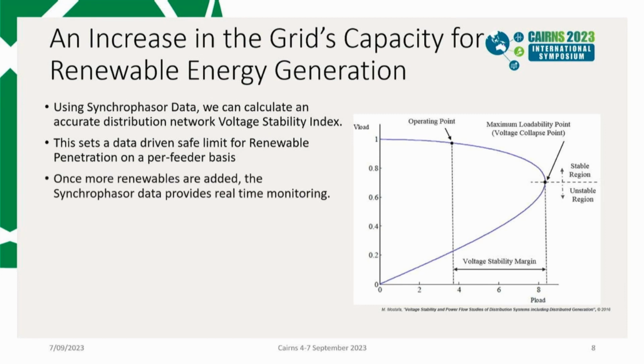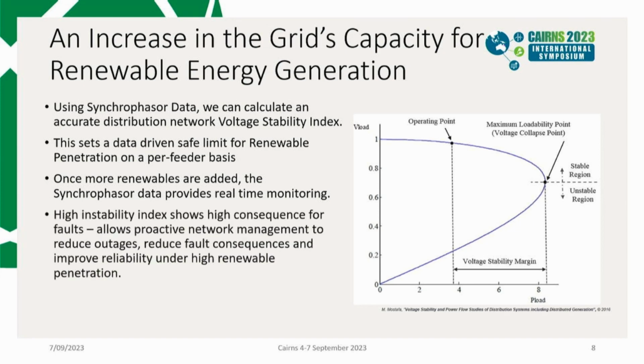With this information in place, as more renewables are added, that synchrophasor data then provides real-time monitoring to ensure that the operating point doesn't approach the maximum loadability point. But all of this gap that we see here is still available to load more renewables onto the distribution network whilst equally managing it. So a high instability index shows a high consequence for those faults, and so it is important to stay within a safe realm. But by having the high resolution data capture on the distribution grid, you can make these decisions based on the evidence that you see on the network rather than relying exclusively on modeling.